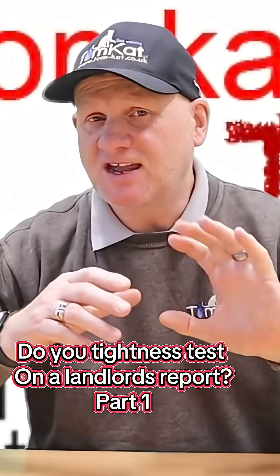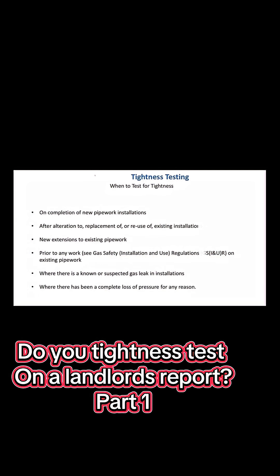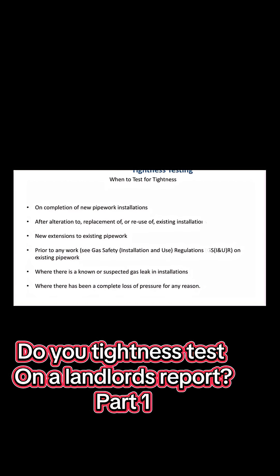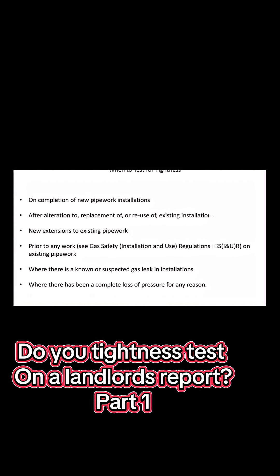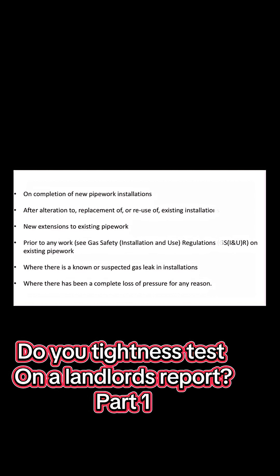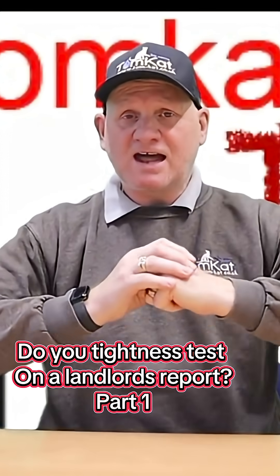Let's have a look at the standards and see when they say we are required to carry out a tightness test: on completion of new pipework installations, after alterations to, replacement of, or reuse of existing installations, new extensions to existing pipework, prior to any work on existing pipework, where there is a known or suspected gas leak, and in installations where there has been a complete loss of pressure for any reason.